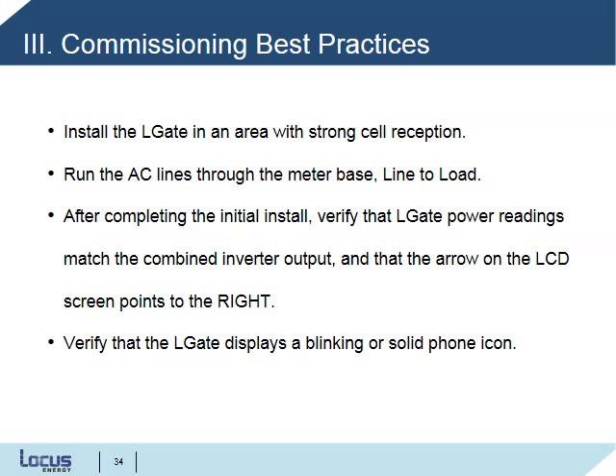To commission the LGate 120 and 320, we recommend installing the LGate in an area with strong cell reception. Always run the AC lines through the meter base, line to load, top to bottom. After completing the initial installation, always verify that the LGate power readings match the combined inverter output by checking what's displayed on the LCD screen.